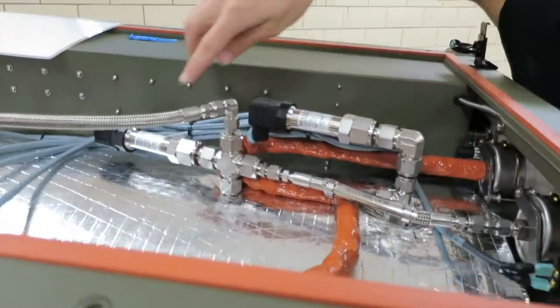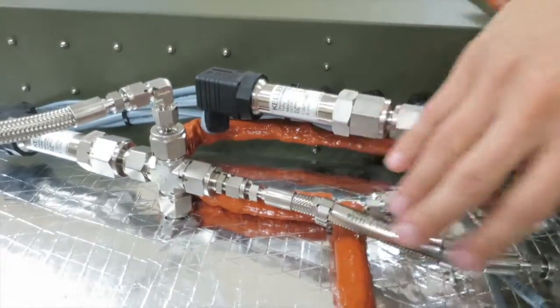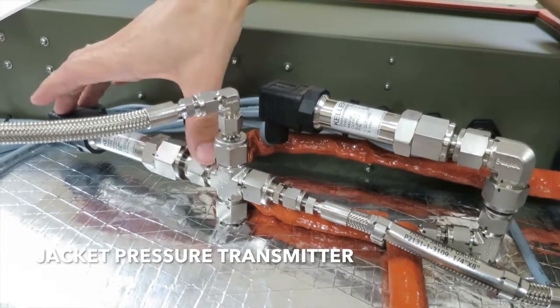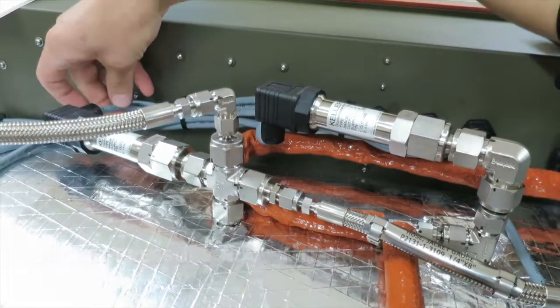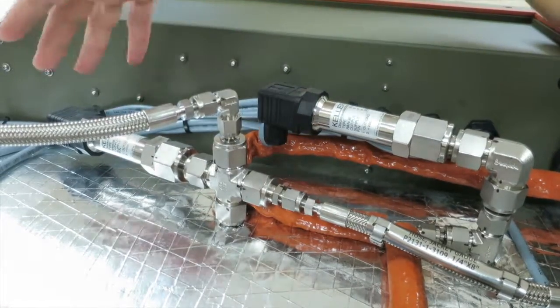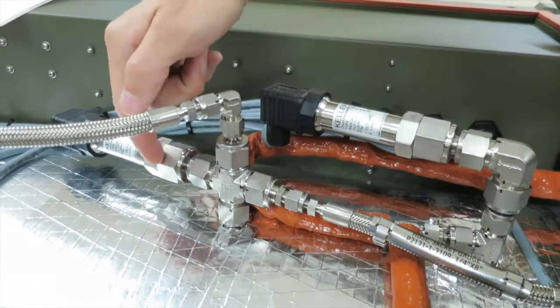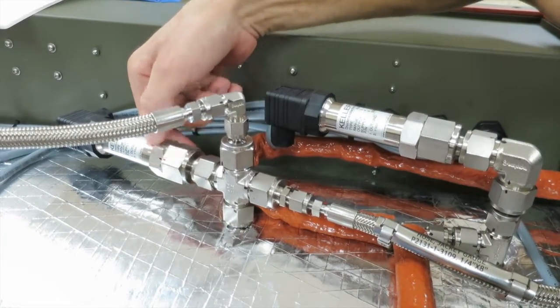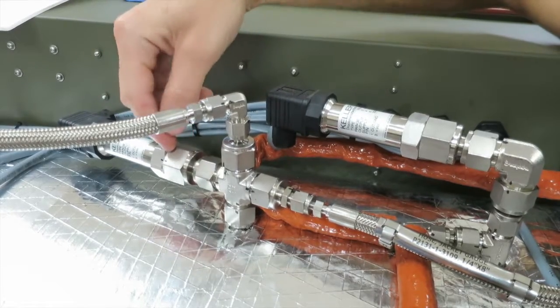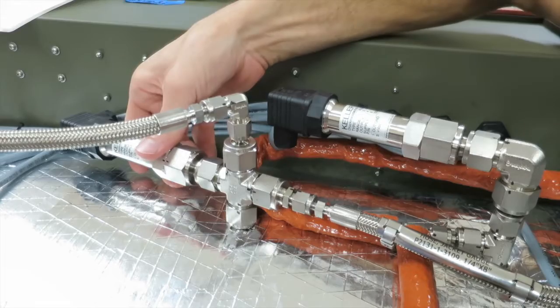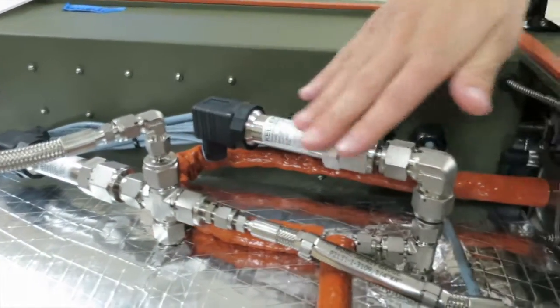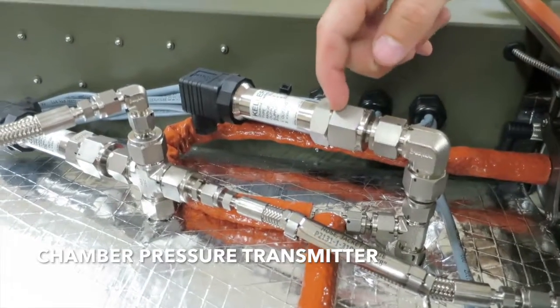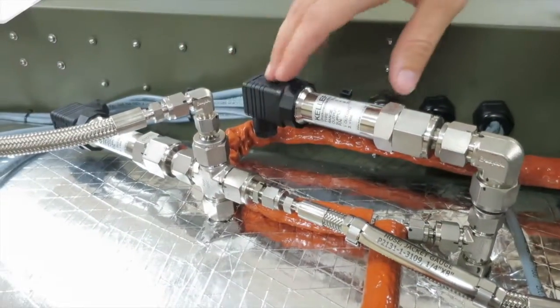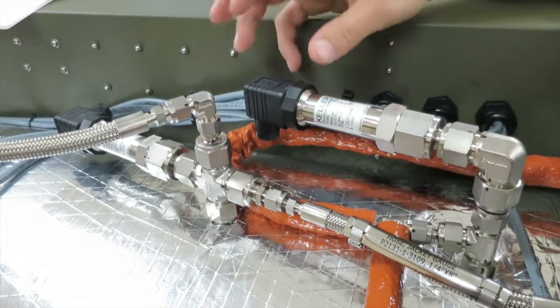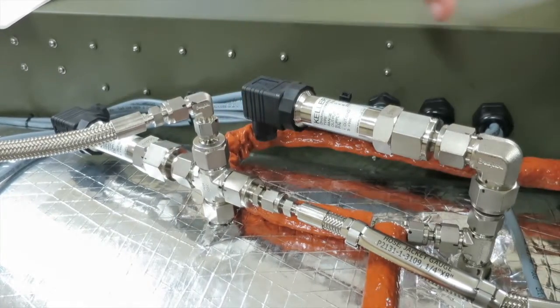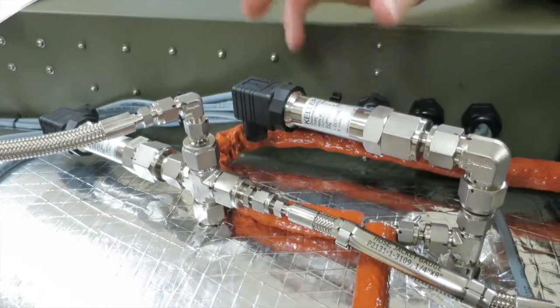So up here we have two pressure transmitters. This is the jacket pressure transmitter, and what it's doing is it's reading the pressure in the jacket and sending the signal to the PLC so the PLC knows how much pressure is in the jacket. There's a little copper gasket that seals this fitting right here, and whenever you do maintenance on these, you're going to want to make sure that copper gasket is sealed and seated fully before you tighten down there. This one is the chamber pressure transmitter, has that same copper gasket right there. And these are actually the same transmitters, so when we send you a replacement part, it'll look identical. It also sends its signal to the PLC, so the PLC knows how much pressure is in the chamber.